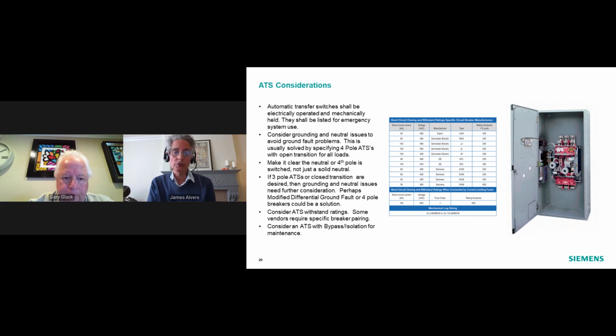If you need 3-pole ATSs or you need closed transition, you really need to consider all your grounding and neutral and bonding issues. You perhaps will need modified differential ground fault or 4-pole breakers. With modified differential ground fault, you'll need to, obviously, wire to the normal system to look at grounds on that side. So, that may affect placement of the board and things like that. The other thing to consider with ATSs is withstand ratings. Some vendors require specific breaker pairings to achieve the withstand ratings. So for instance, there's an example here of a withstand rating chart with the paired breaker associated for that particular ATS.